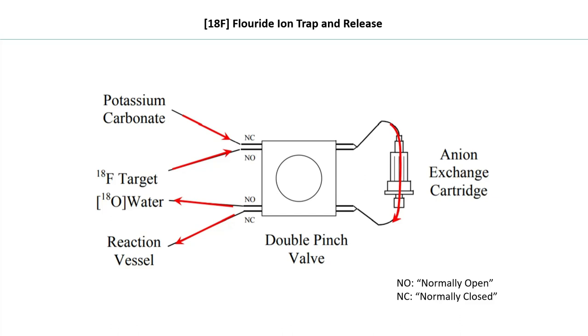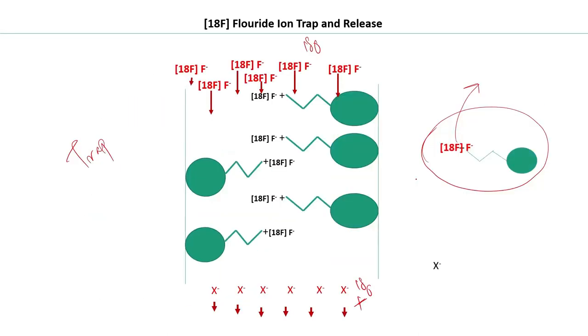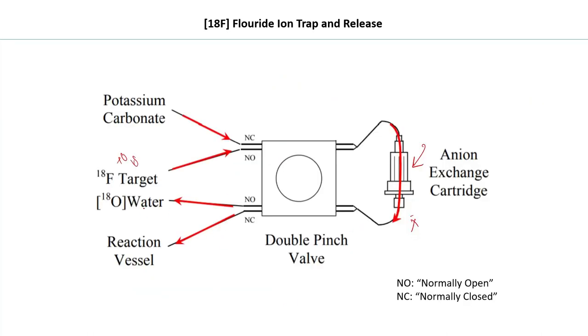Looking at the hardware: the F-18 in O-18 water from the target passes through a normally open pathway into the anion exchange cartridge, where all F-18 ions are trapped. The output at this stage yields O-18 water and counter-ion X. Next, a normally closed channel is opened and potassium carbonate solution is passed through, releasing the trapped F-18. In the reaction vessel, we collect F-18 fluoride ion with potassium as the counter-ion, since potassium carbonate was used — the carbonate binds to the bead and potassium becomes the counter-ion for fluorine.